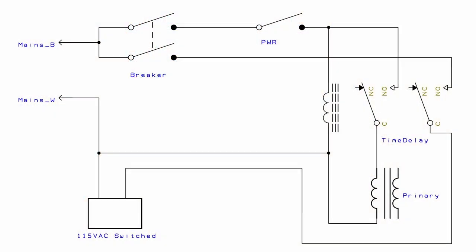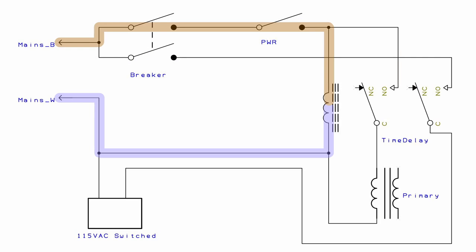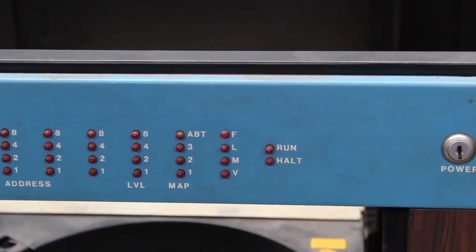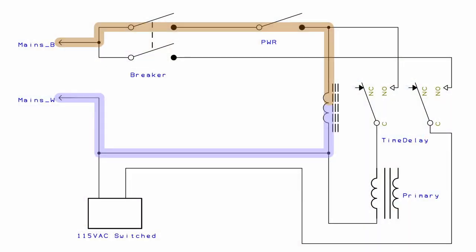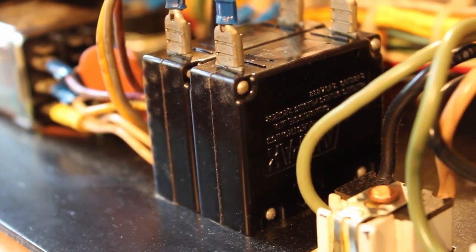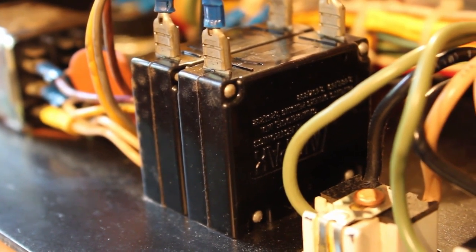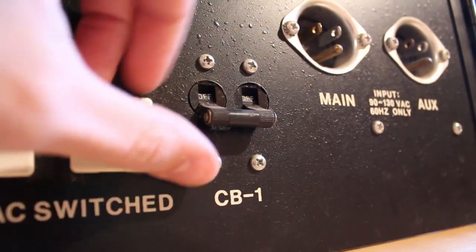So having said all of that, we've got our time delay relay that essentially kicks on as soon as we flip the power switch and the breaker. So we can see that coming out of the coil of our time delay relay, we go to the power switch, and this is the key power switch that's on the front of the unit. And then coming out of that power switch, we come all the way back to the main breaker here.